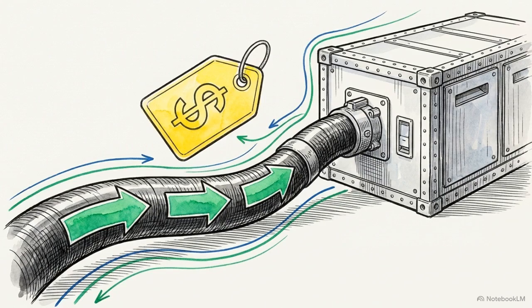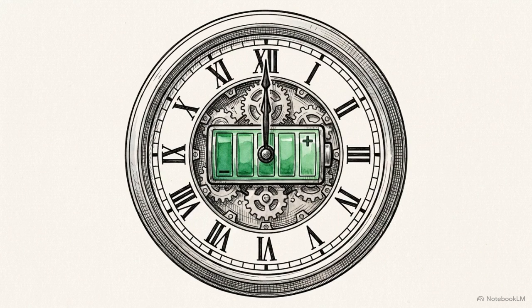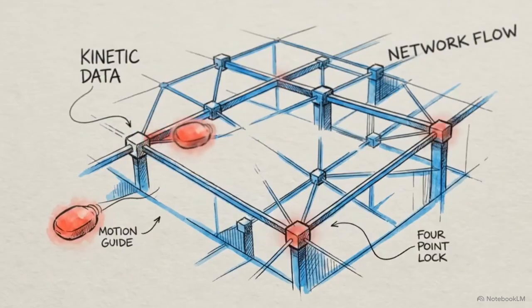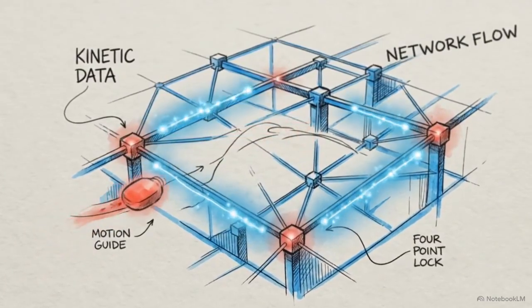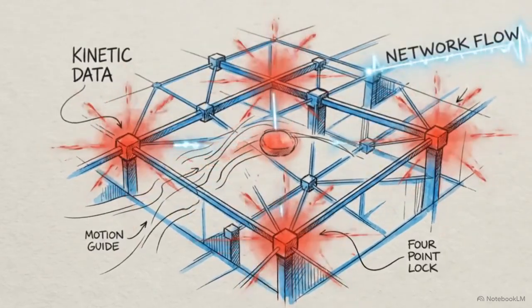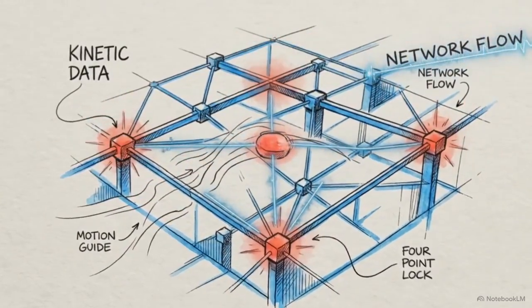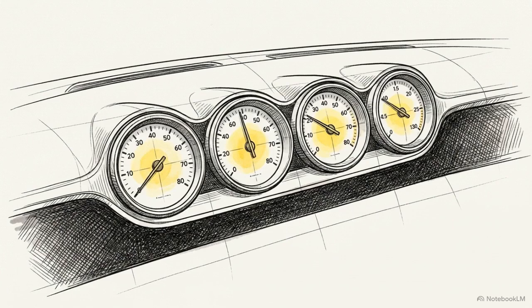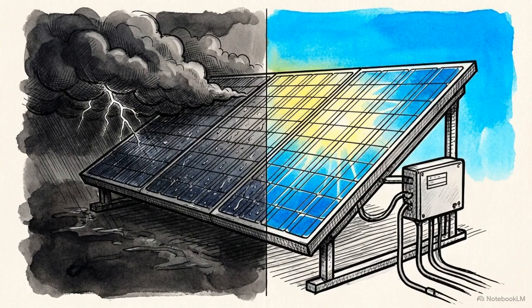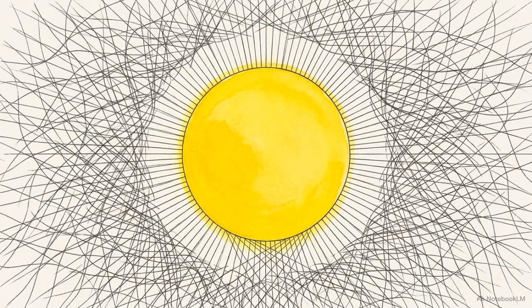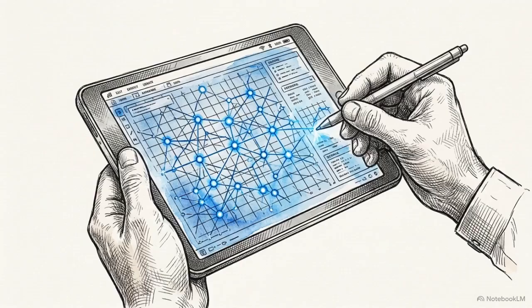calculated cost. This formula operates under strict hardware constraints, particularly the requirement to recover the battery's cyclic state of charge by midnight. The marine predators algorithm takes this massive equation and hunts for the optimal 4-parameter sequence that minimizes the final sum of all these competing penalties. Because the parameter vector is so compact, the algorithm computes the minimum cost with extreme speed, allowing the grid to react to rapid changes in cloud cover or user demand. The optimization engine successfully translates a tangled web of hardware limitations and environmental goals into a single, highly solvable mathematical target.